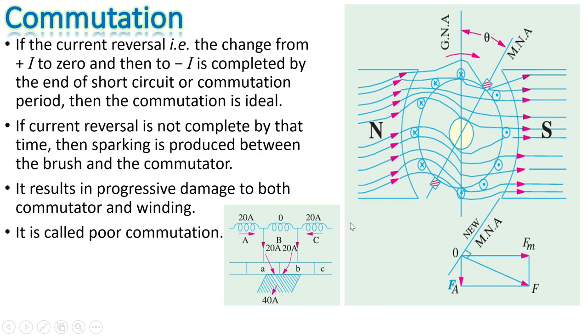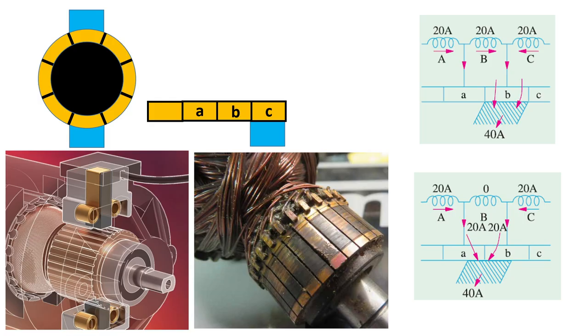If the current reversal — that is, the change from positive maximum value (+i) to zero and then to negative value (−i) — is completed by the end of the short-circuit or commutation period, then the commutation is said to be ideal. If current reversal does not complete by that time, sparking is produced between the brush and the commutator. This results in progressive damage to both the commutator and the winding, and is called poor commutation.